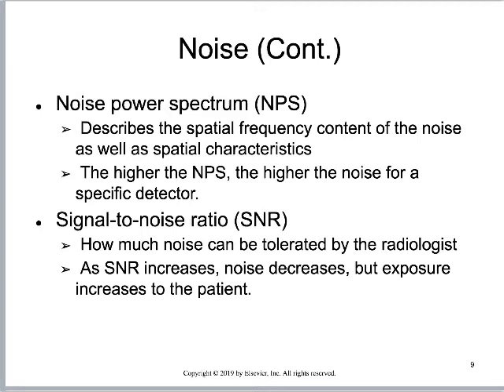The noise power spectrum describes the spatial frequency content of the noise as well as its spatial characteristics. As the NPS gets higher, the noise is higher for a specific detector, and that noise would eventually start to influence whether we can see tiny objects. Signal-to-noise ratio asks: how much noise can be tolerated? As the SNR increases, that's a good thing — more signal and less noise. Generally, with almost all digital systems, to increase the SNR you have to increase patient dose.